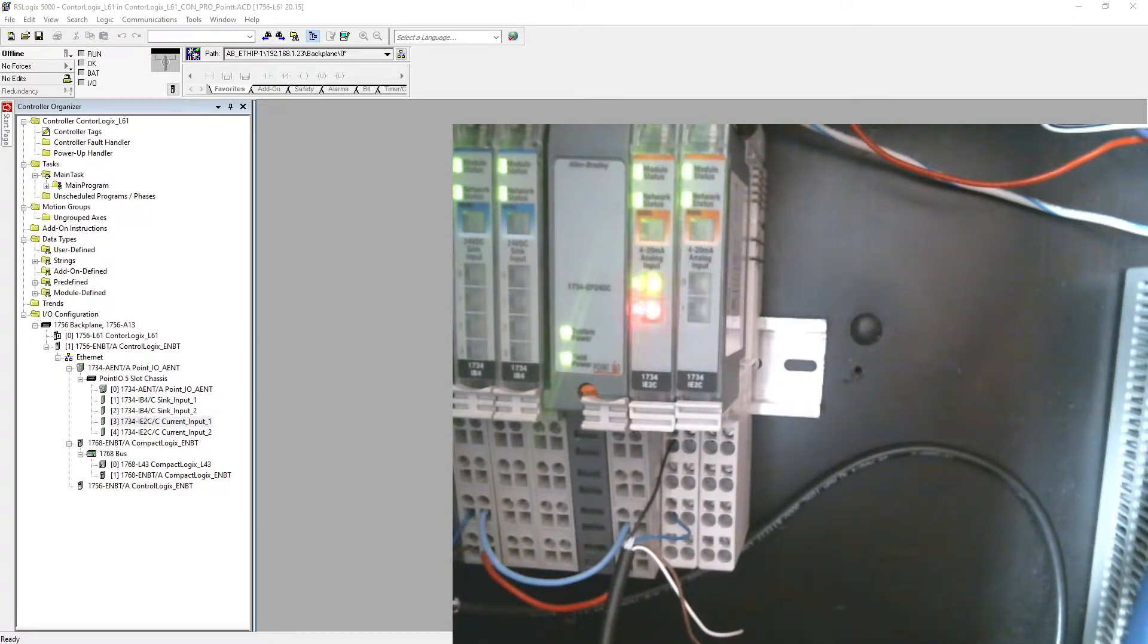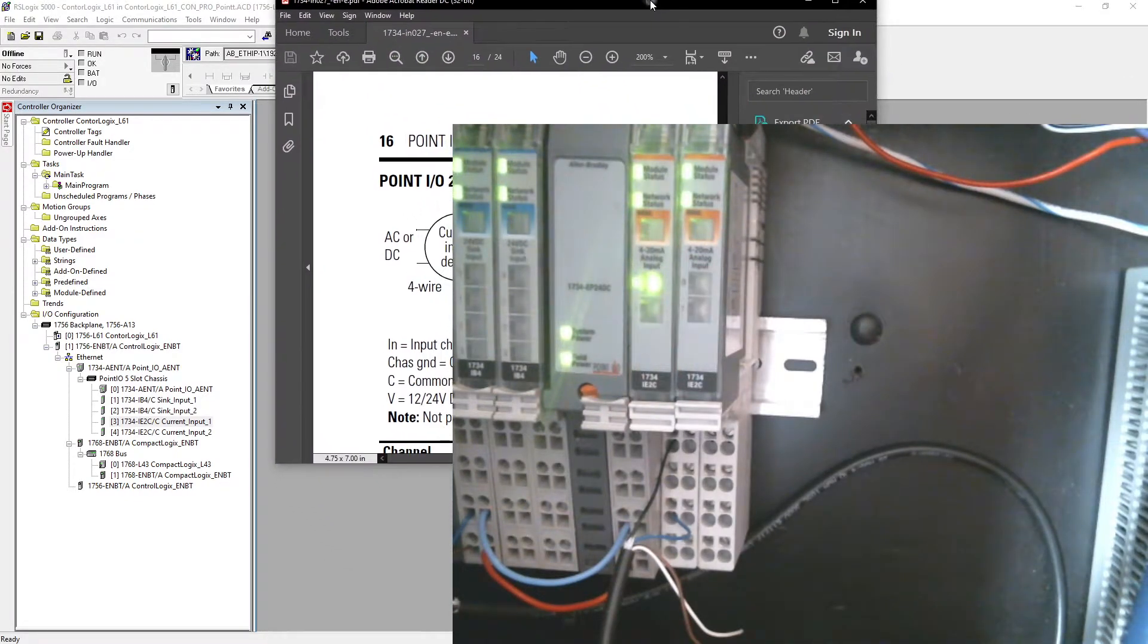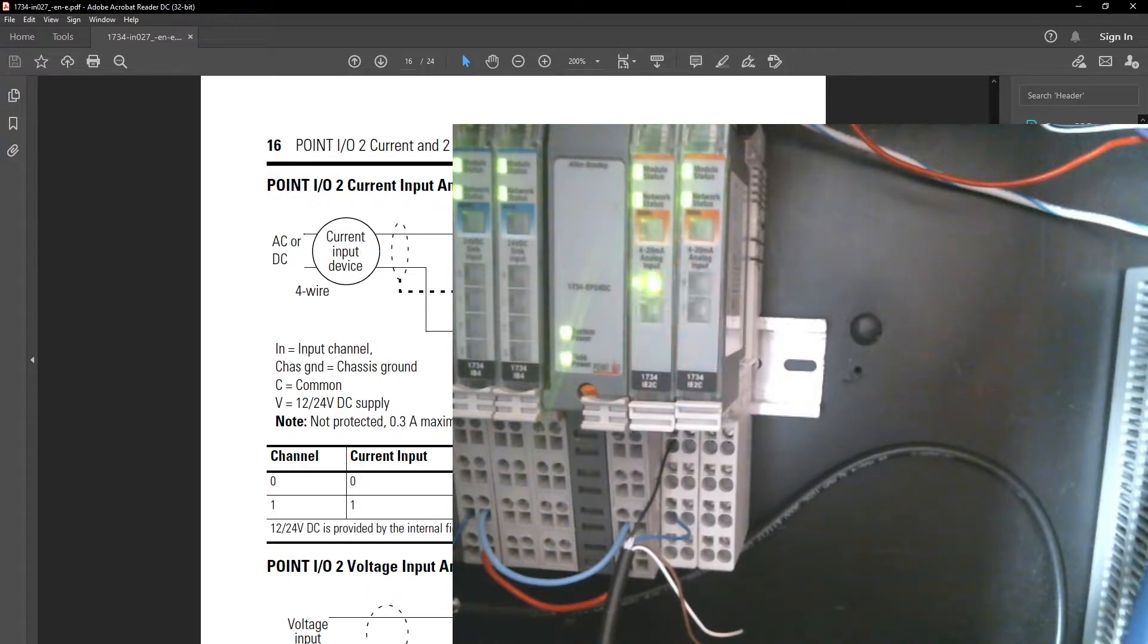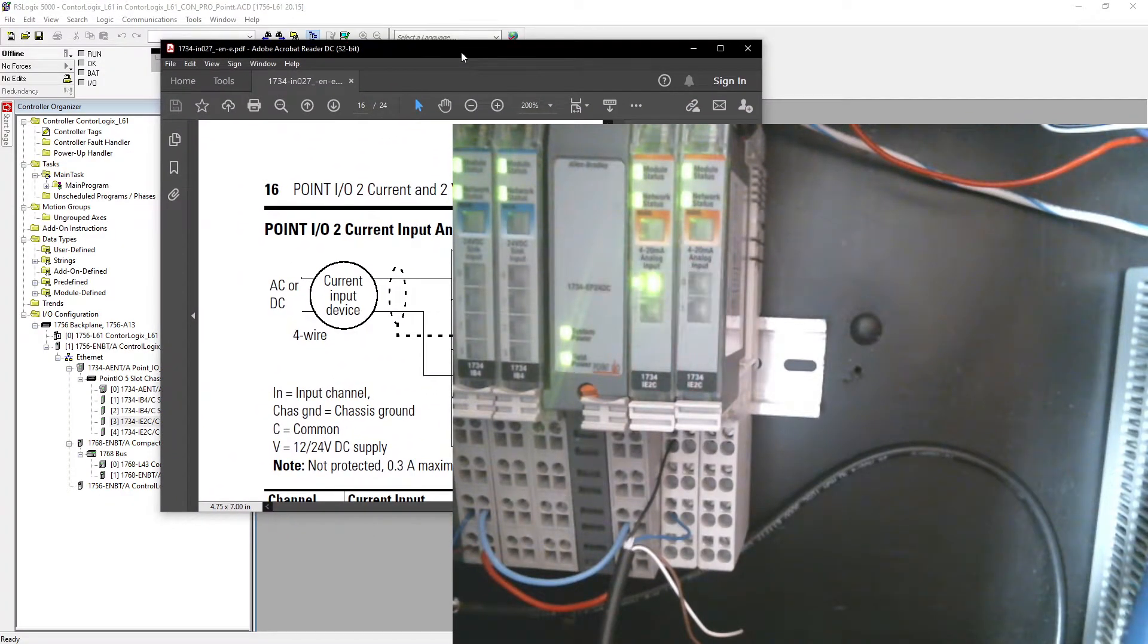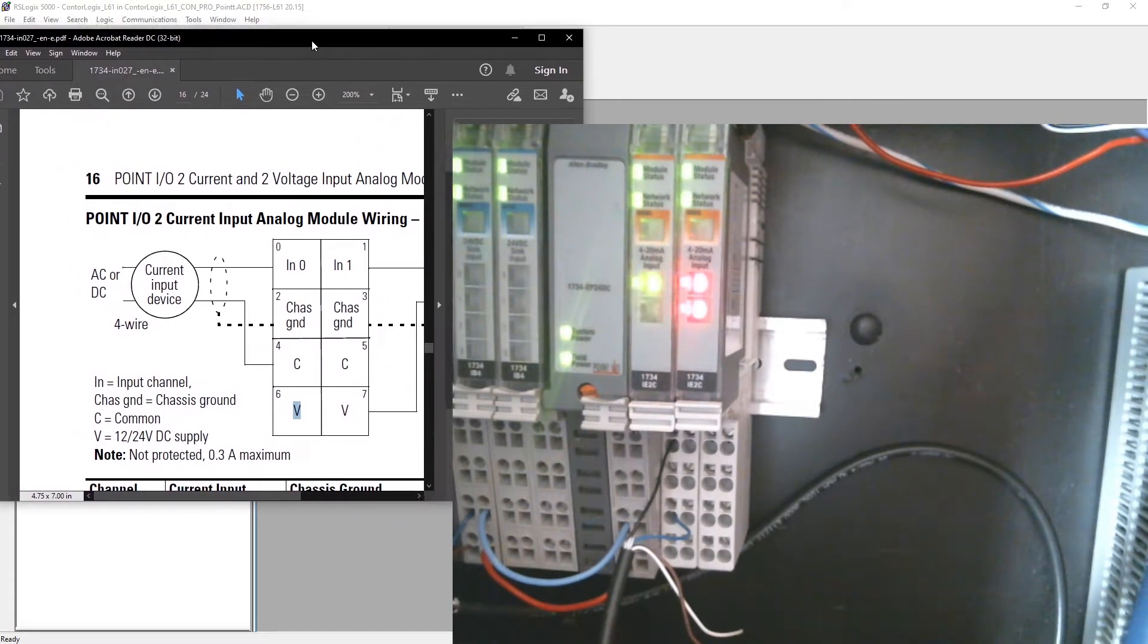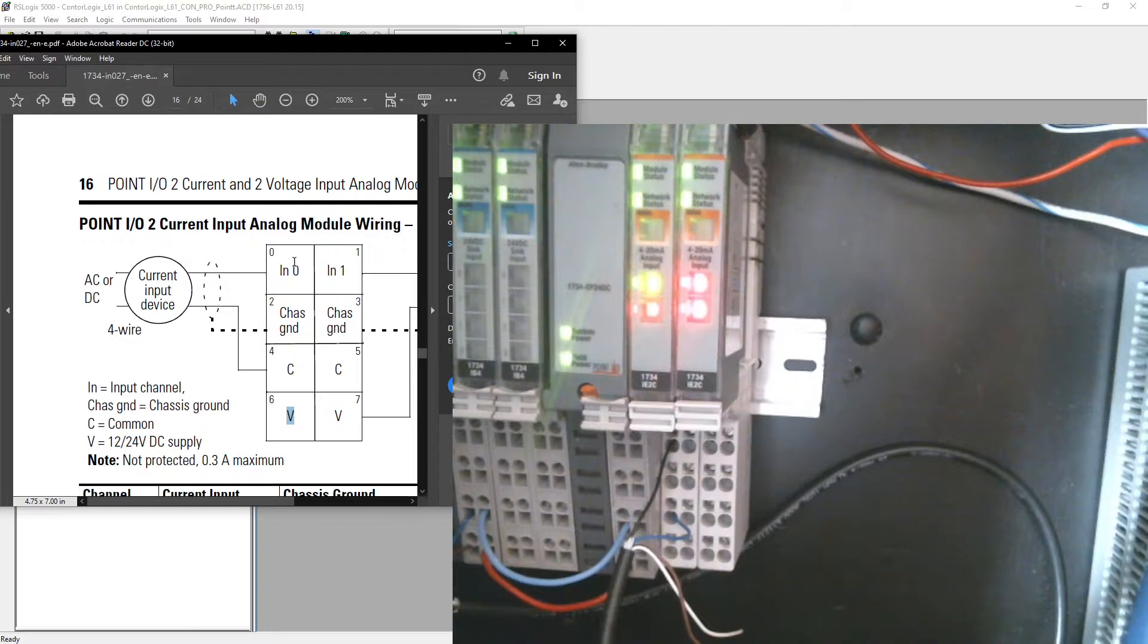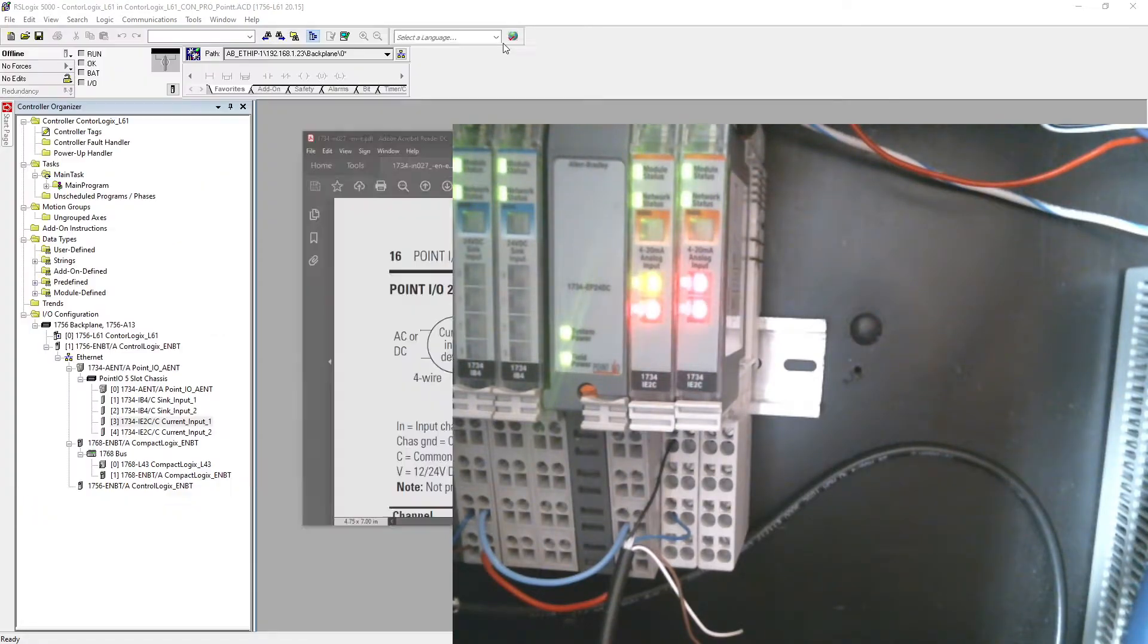That means there is no connection between them. Let me show you my PDF which has all information about this card 1734-IE2C. The first one is input, then second one is also input, then chassis ground and common and voltage. What we did here, we connected to this zero and common. On zero I connected a black wire as you can see on screen, and on number four I connected my common which is coming from my voltage and current generator.